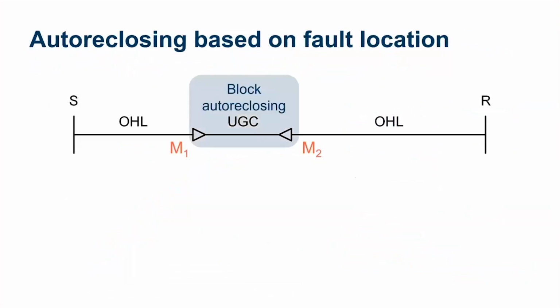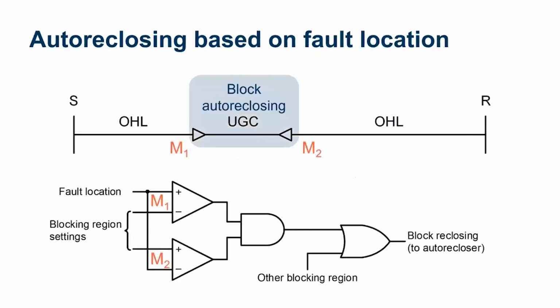This is an example of what our logic will look like if we're just going to be blocking for this underground section, for this underground cable. We're going to define blocking regions within the relay. You can see if the fault location is greater than point M1, and it's also less than point M2, we're going to declare that on the underground section, and we're not going to allow our reclosing relay to reclose for this fault. Now, this can be used not only for underground lines. We can use it for sections of overhead lines. You could use that over here on the second part of this overhead line. So not only for underground lines.